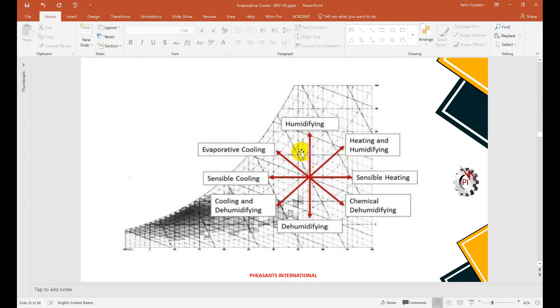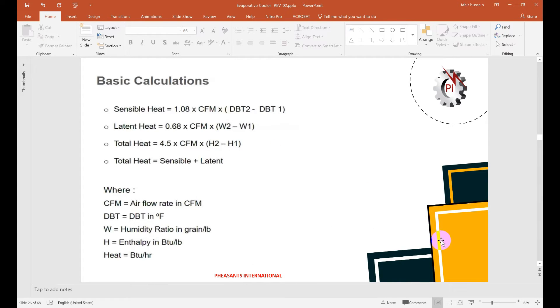Our evaporator cooling system works on the portion of the chart where the wet bulb temperature remains constant and the enthalpy also remains constant. There are basic formulas: sensible heat = 1.08 × CFM × (DB2 − DB1), where DB2 is outlet temperature and DB1 is inlet temperature. Latent heat uses W2 and W1, the specific humidity at outlet and inlet conditions. Total heat = 4.5 × CFM × (H_outlet − H_inlet), using enthalpy values.